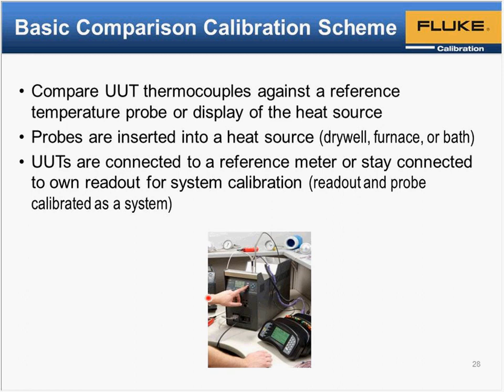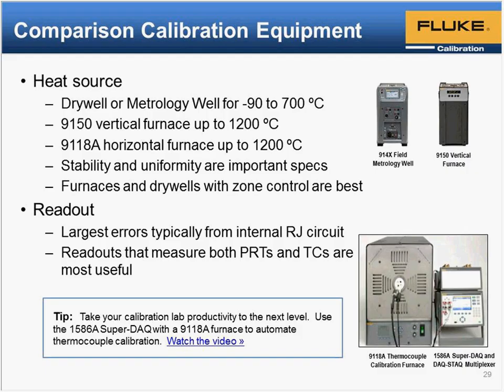UUT probes are connected either to a reference meter provided by the laboratory, or they stay connected to a readout that's provided with them, so that a system calibration can be done. Let's say that the majority of thermocouple calibrations happen in something like the Fluke metrology well. These are calibrated furnaces, and the display has an assigned accuracy.